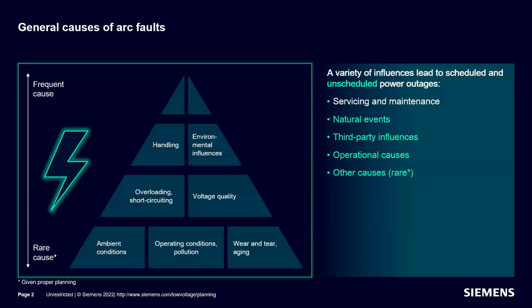Tell me how. If I don't have an ACB in place, if I don't have an RCCB in place, the fire may happen because of an earth fault, at 100 milliampere or 300 milliampere, apart from what the RCCB does for human safety at 30 milliampere. If I am not installing an RCCB, how can it save me? If I'm not installing AFDD at particular places as per NEC, then how is IoT going to save me?